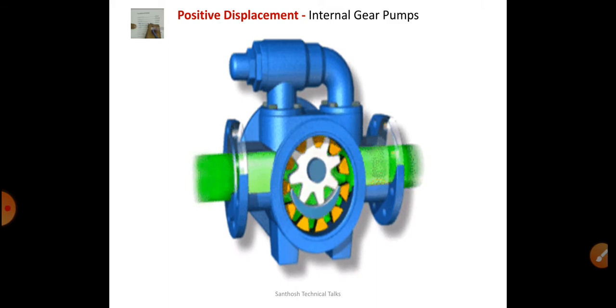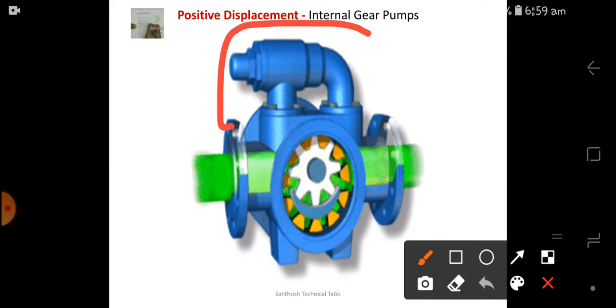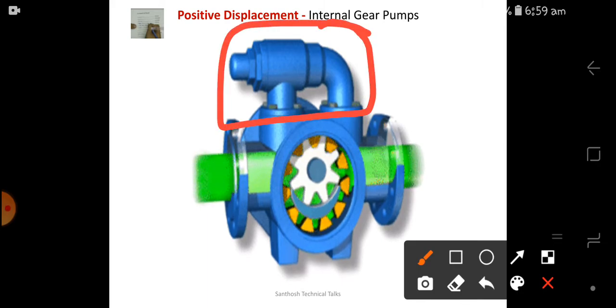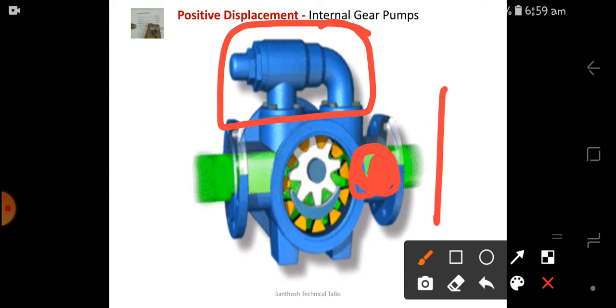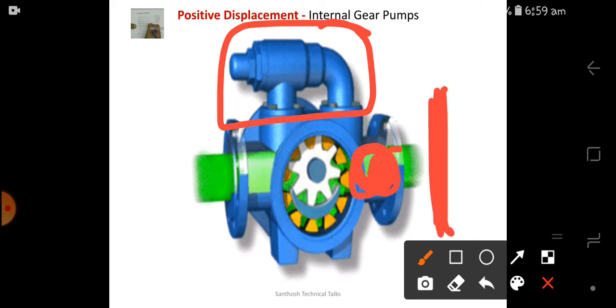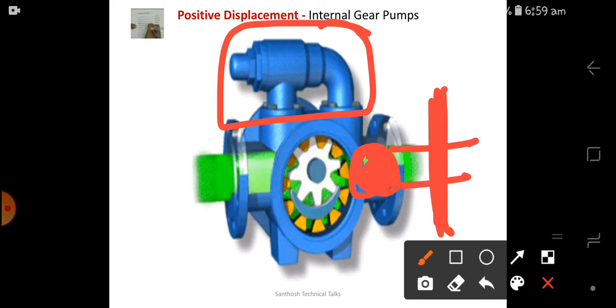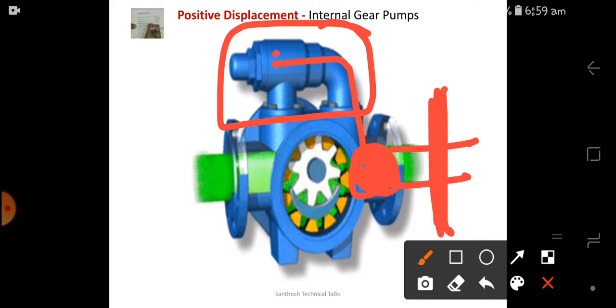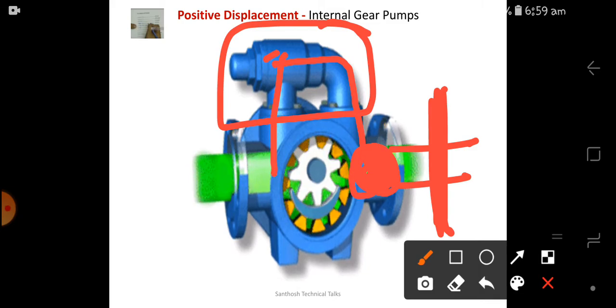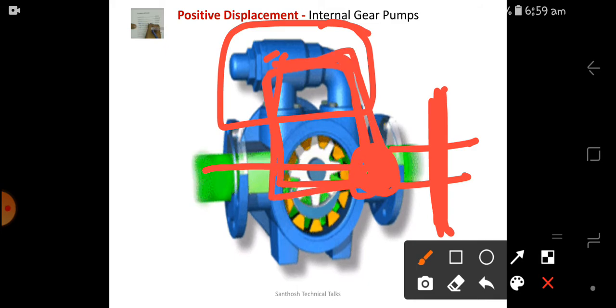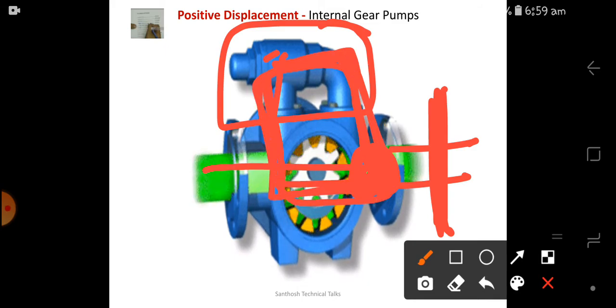One ring gear is there and another pinion is there. So both gears are mated internally. So that is how it has been done. And here is the safety valve. This is the safety valve. At the delivery end, if a huge pressure is built up, since the delivery valve is closed, the high pressure will transfer to the pressure relief valve and be transmitted to the suction end. Therefore, fuel or fluid is transferred between the suction and delivery of the pump.